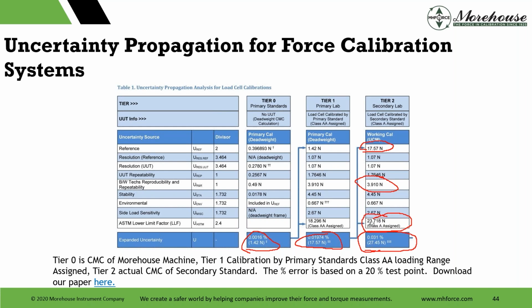Basically, what I'm saying is on tier 2, we said, hey, let's take the absolute best scenario that could even be possible, likely never going to be probable, and let's see the best case we could possibly get. And we got to 0.031%. So what that says is if you're using dead weight, you can get much better than using the secondary standard, right? Calibrate dead weight 0.016, calibrate the load cell, you get 0.02 around there. Now you have to absorb that uncertainty, and assuming nothing else changes, which it absolutely will, the best I could get is 0.03.